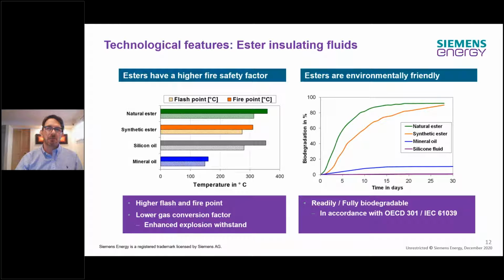Another feature we decided to use from that toolbox of measures was using an alternative fluid instead of mineral oil. So we decided to use synthetic ester, which has two key advantages over mineral oil. The first and most important one is that it offers enhanced fire safety. The second one is that it is environmentally friendly. And on the left-hand side of the graph, you see that the fire and flash points of ester fluids are much higher than those of mineral oils. That means the likelihood of igniting is much lower than in the mineral oil case.